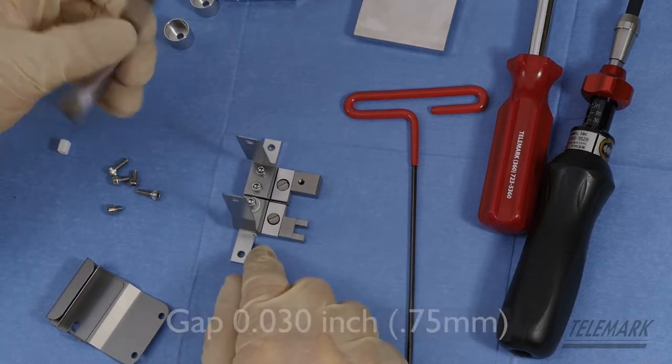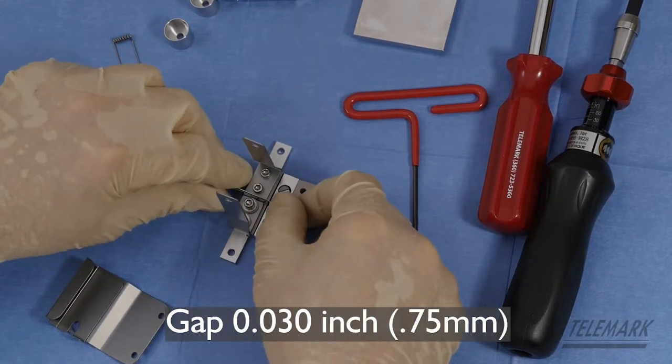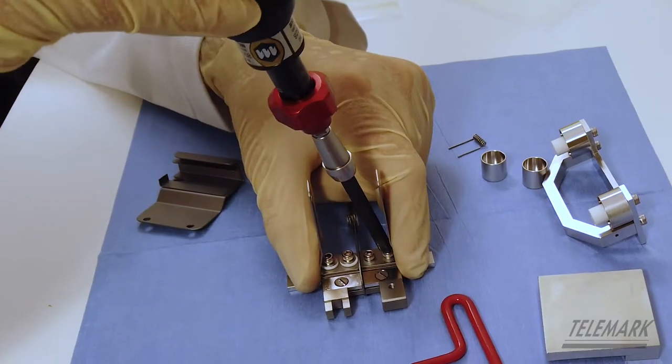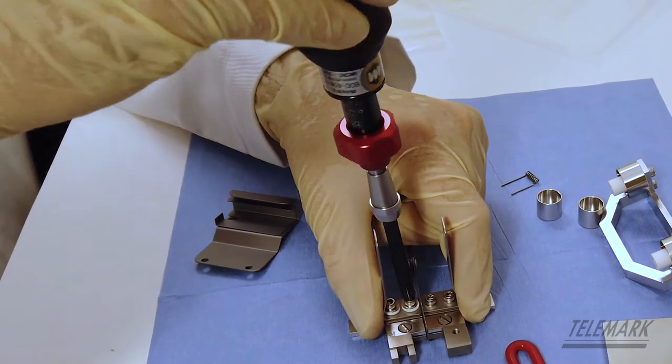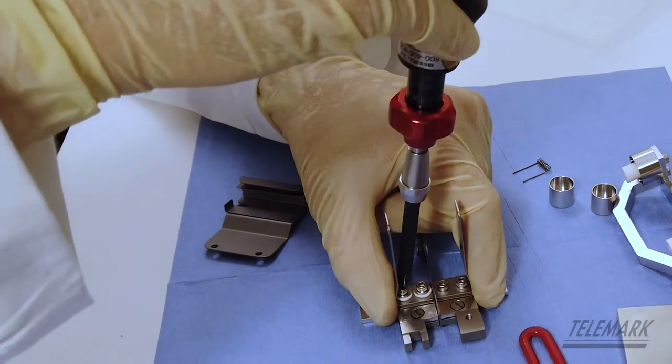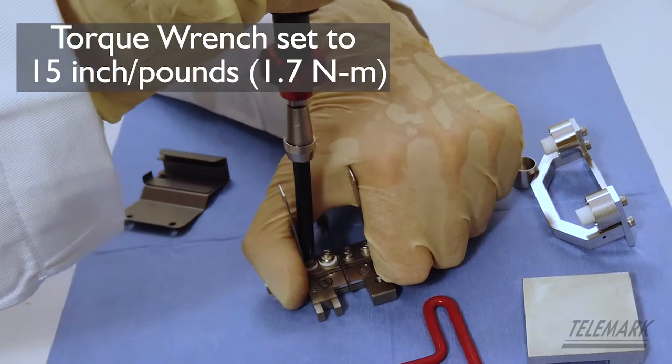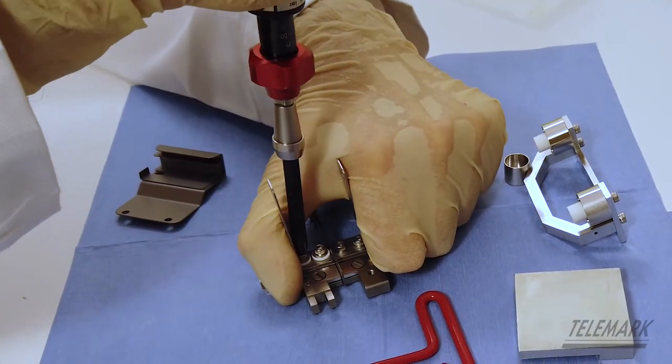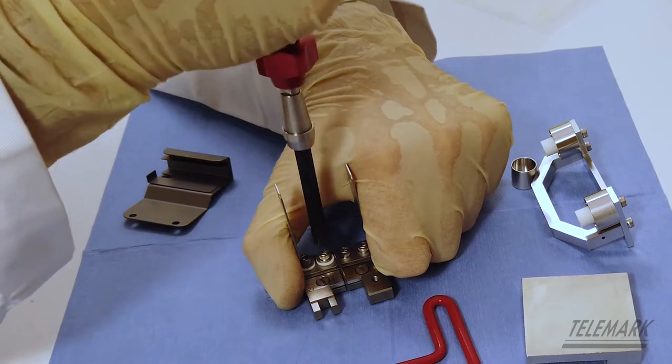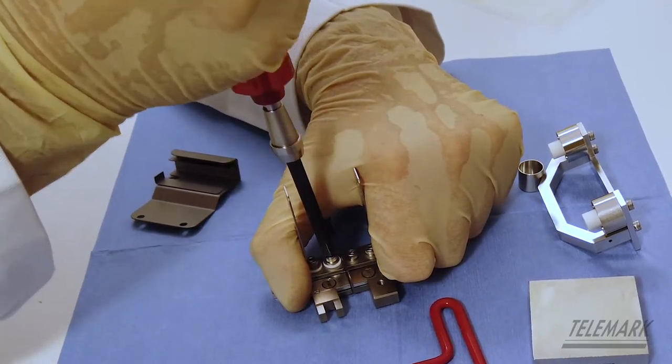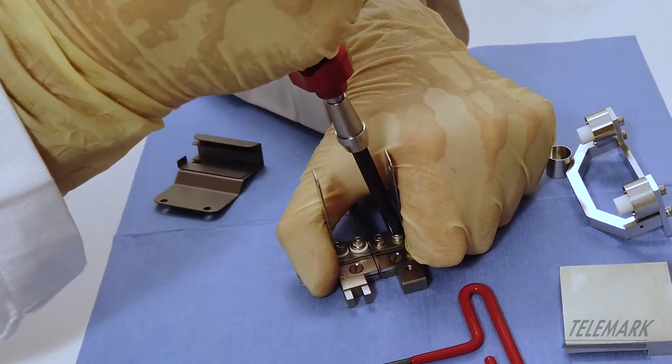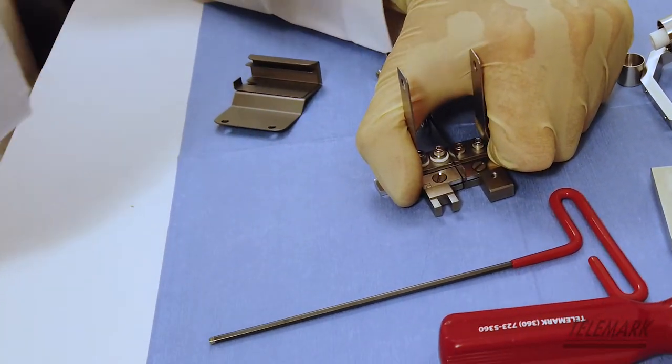Grab a feeler gauge. In this case they're set up for 30 thousandths, so you can gap the cathode blocks at 30 thousandths. Grab the torque wrench and snug them all down. Pinch on the cathode blocks, forcing them against the feeler gauge, and lock it all down.